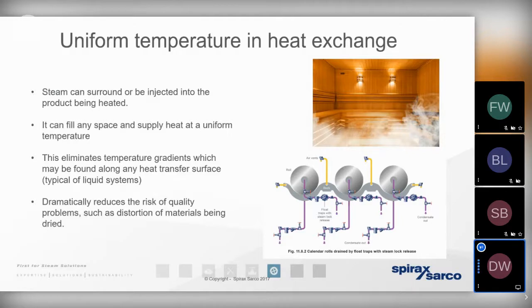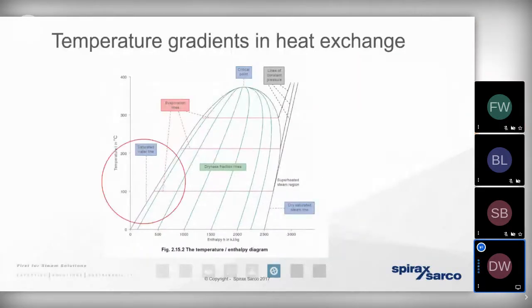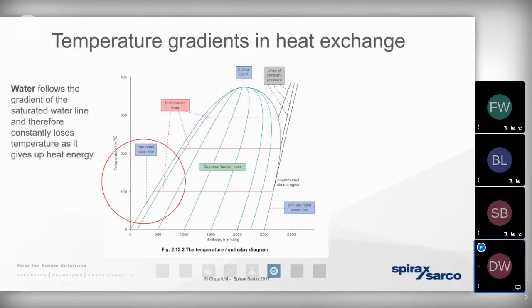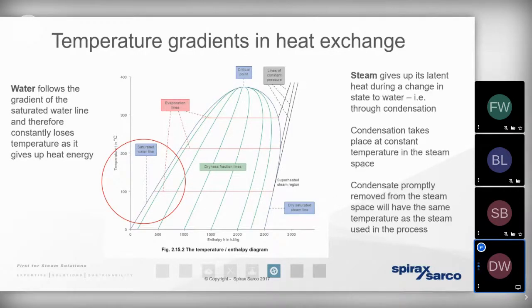So just to remind ourselves, when steam's being used to heat a process, it's that enthalpy of evaporation. It's the latent heat. It's the energy that we added to the boiling water. That's the energy that passes from the primary side to the secondary side. And we can only use this latent heat energy, this enthalpy of evaporation, to heat the process. It's approximately 75% of the total heat energy. So that means that the energy that we cannot use, the energy that's left behind, that's retained within the condensate, the liquid, that's about 25% of the total heat energy. We refer to that as the sensible heat.